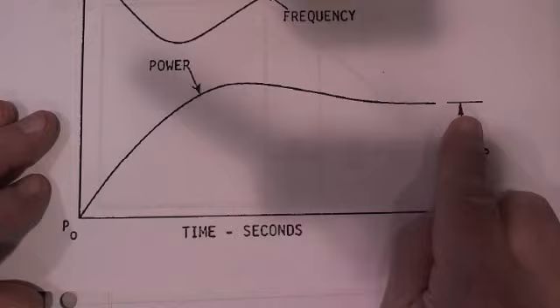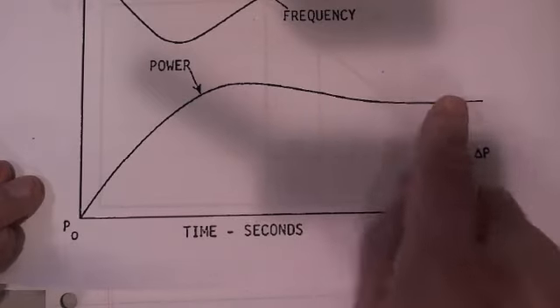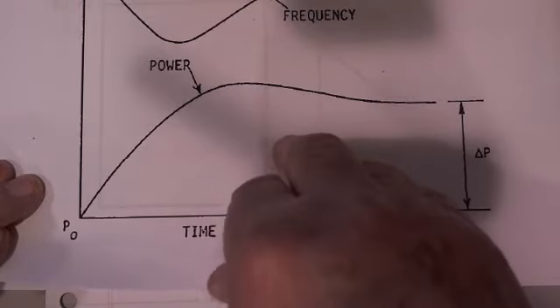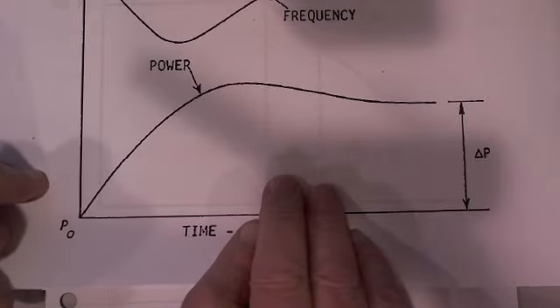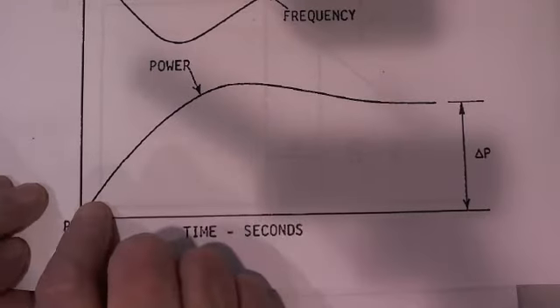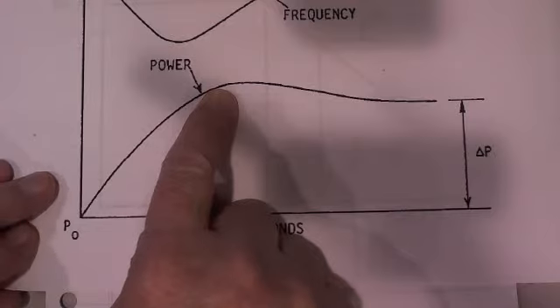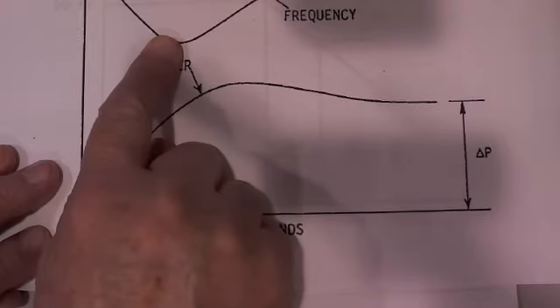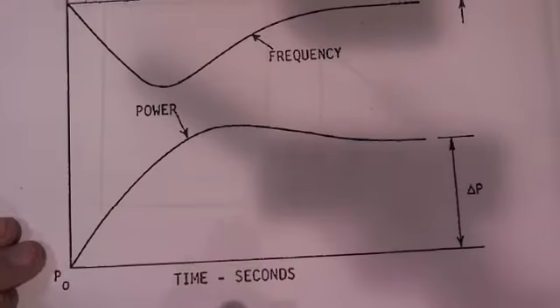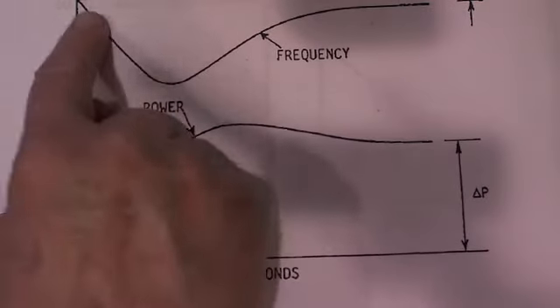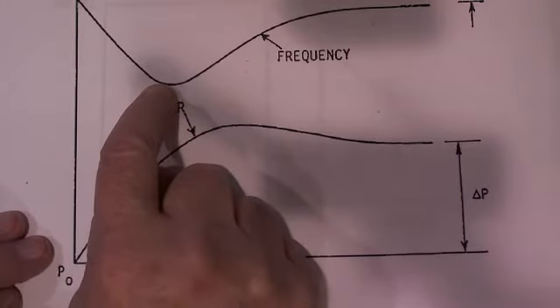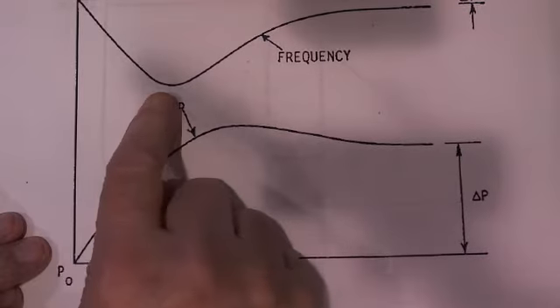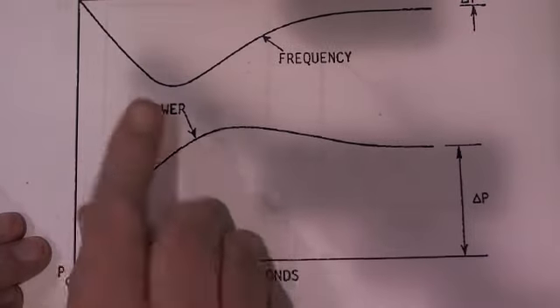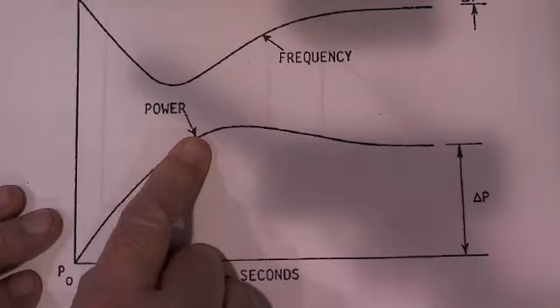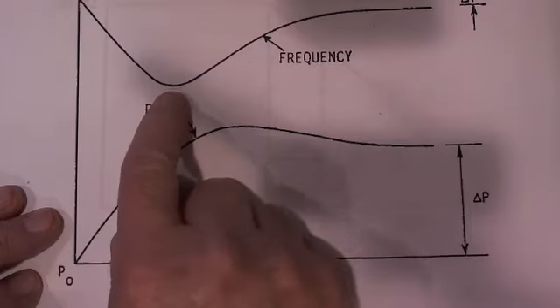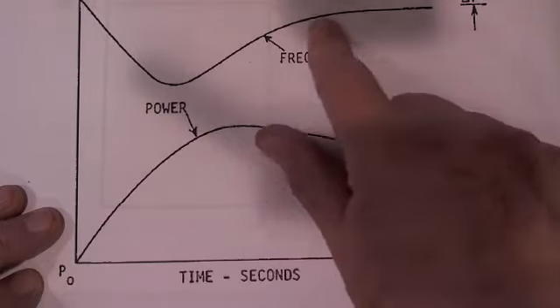So when you have a delta P, you want to get more power out, and as soon as you want more power, you put more load on the motor, and the frequency drops. The frequency drops because you're actually stealing energy from the rotating kinetic energy of the generator. The frequency drops.